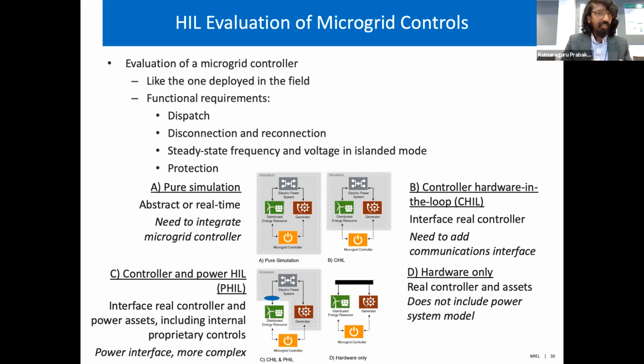That hybrid approach is the niche of our Energy Systems Integration Facility, where we leverage our megawatt-scale experimental facility, bringing in the same inverters and other power devices that will be installed in the field to evaluate both the power hardware piece and the controller hardware piece. The last approach is hardware only, which is rarely used because it requires emulating the whole microgrid, becoming extremely expensive. For this project, we used a controller hardware in the loop and power hardware in the loop setup to evaluate the microgrid controller functions.